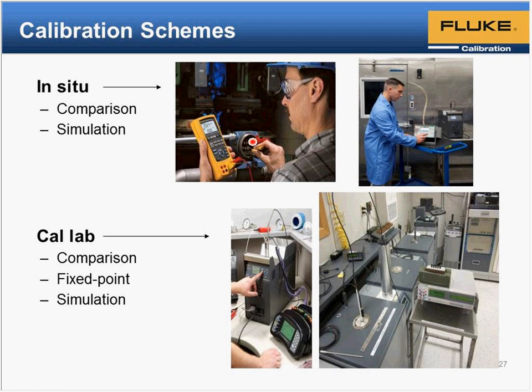But we just got done talking about all the things that could cause thermocouples to change a lot. So if you can also verify the thermocouple measurement, great, but it can get very tricky in on-site calibrations. Now in our lab, it's a lot easier. You have a lot more options. In our laboratory, we calibrate thermocouples by fixed point, but we only calibrate noble metal types, type R and gold platinum thermocouples.